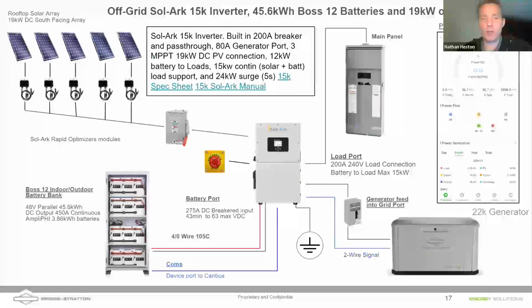With use of the 2-wire start, so that the Sol-Ark automatically starts the generator when it needs it. I mean, that's the added complication for me. When I program the smart loads port to say I've got a generator there, that's what's automatically starting the generator when the batteries get low, or if the grid goes down, we're going to use the batteries first. We don't want to start up that generator and use that more expensive fuel.